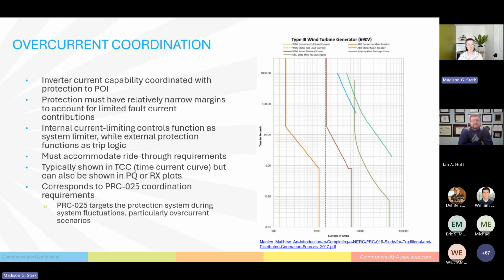The next thing we hit is this stator full load current and then this stator main breaker. This is the maximum full load current, steady state operations, that the stator portion of the wind turbine can output. What that means is that these 2 elements, the yellow and the red, are not really correlated at all. They're like 2 separate elements that require separate coordination.